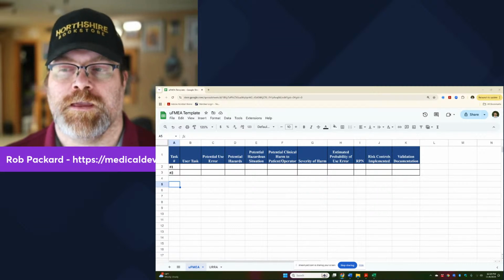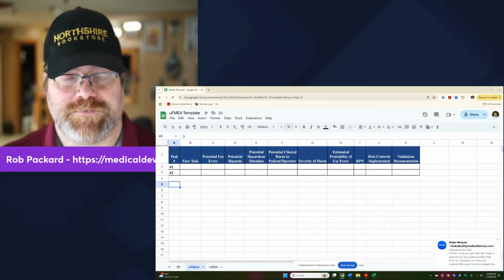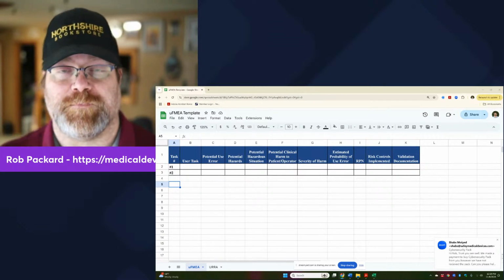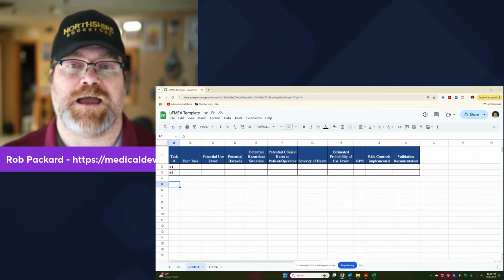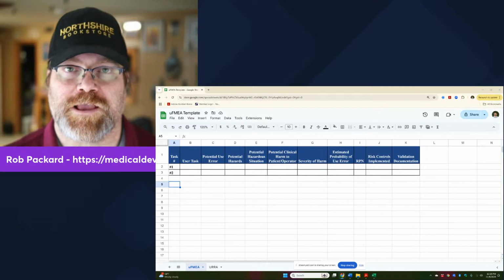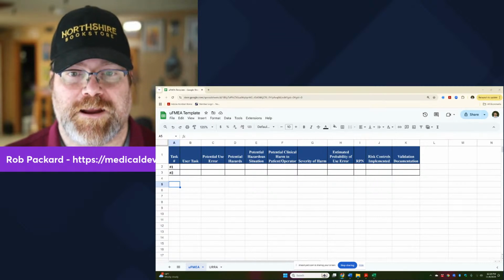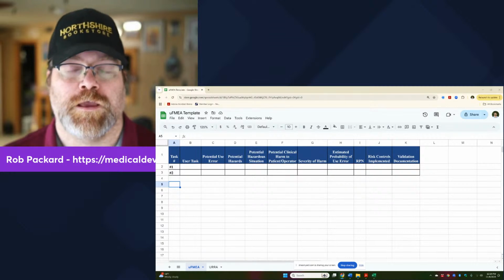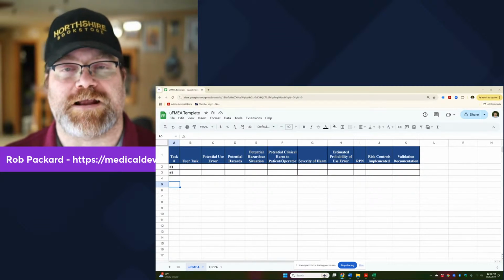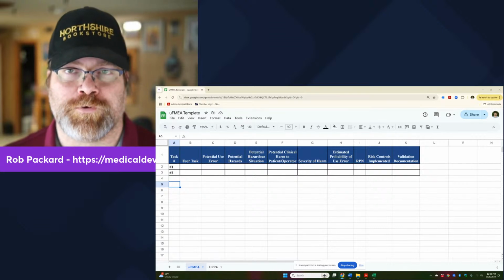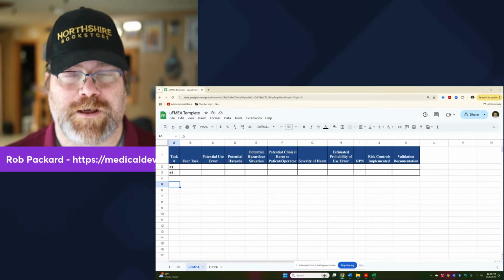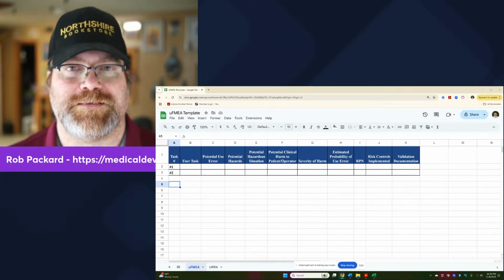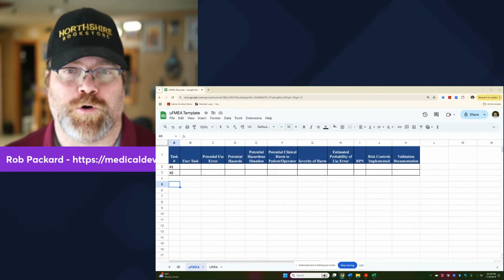If you have a design failure modes and effects analysis, design FMEA or little d FMEA, you typically take out the column for detectability, because it's not a good practice to rely on the detectability of a design error because it's too late. You've already delivered it to the customer. But for process FMEAs, they use this third factor, detectability, because they typically have in-process automated inspection that prevents it from getting to the customer. You've caught it during manufacturing. If you don't catch it during the design process, it's too late. It's already gotten to the customer by the time they detect it. So that's too late. It's not a proactive risk control.